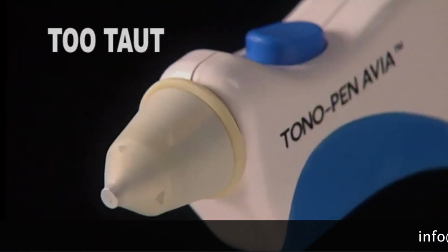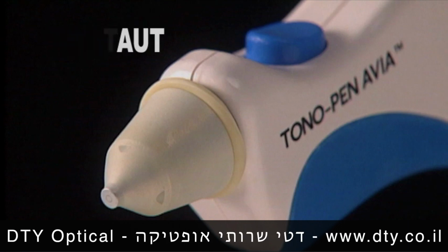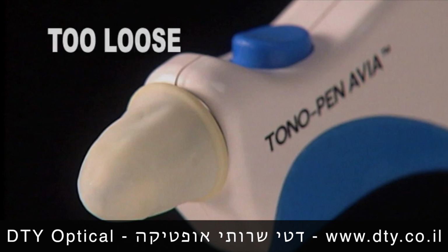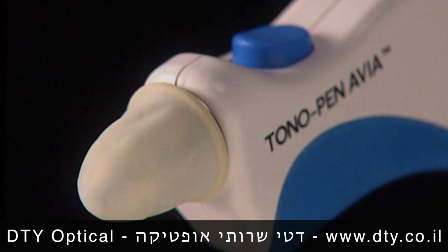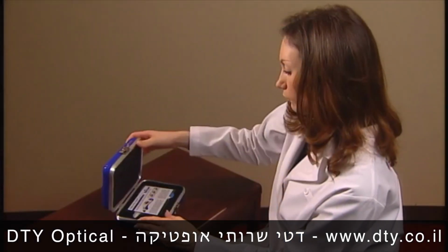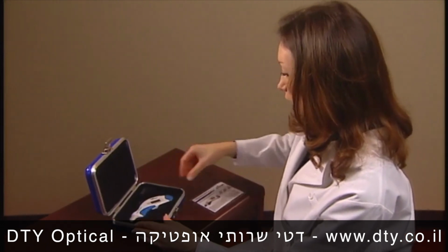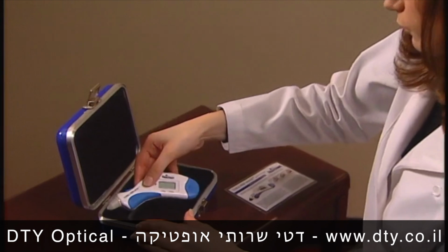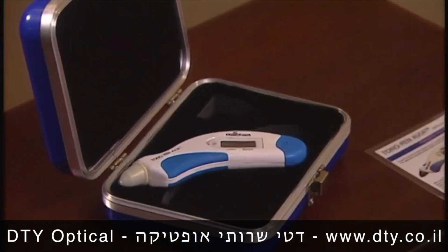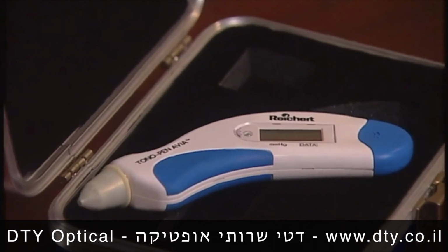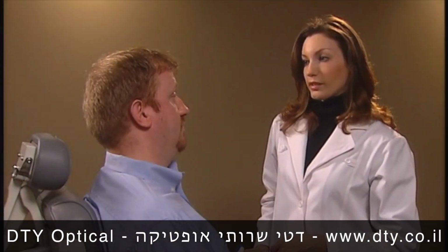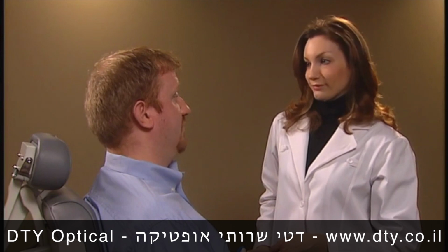If too taut, the OcuFilm tip cover might introduce resistance in the micro movement of the transducer post, which could cause readings that are too high. On the other hand, tip covers should not be too loose so that they form a fold or a crease over the transducer. Adjust the tension until no pleats are evident. It's also important that you bring the Tonopen Avia to room temperature before use, especially if it has been stored in an environment which is subject to temperature extremes. If your patient is prepared, you are now ready to start the measurement process.